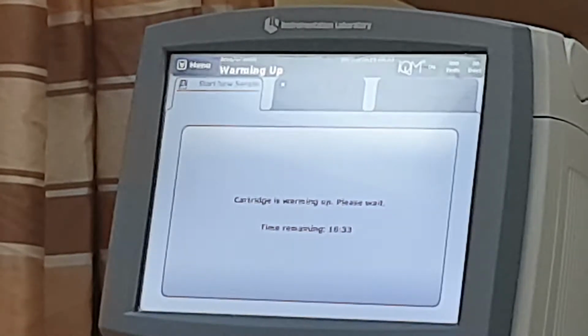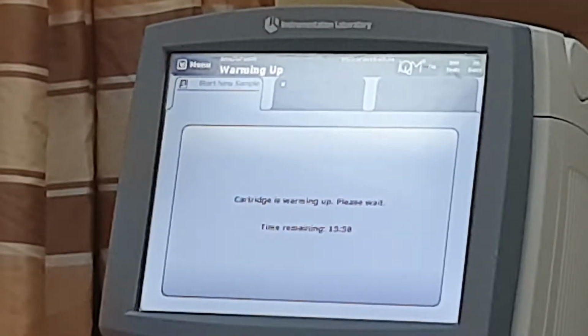We will start with 4, 3, 2, 1. So what is the CVP? CVP is calibration, verification, product. 4 and 3 are low and high hematocrit, and 1 and 2 are low and high co-oximetry. The other parameters are pH, CO2, O2, sodium, potassium, chloride, calcium, glucose, lactate, and hemoglobin. If I get a pass for all of these CVPs, that means the cartridge is working well, if the result is within the range, because for each level we have a range. So if my result is within the range, it passes. After that, you are allowed to run samples on the machine.